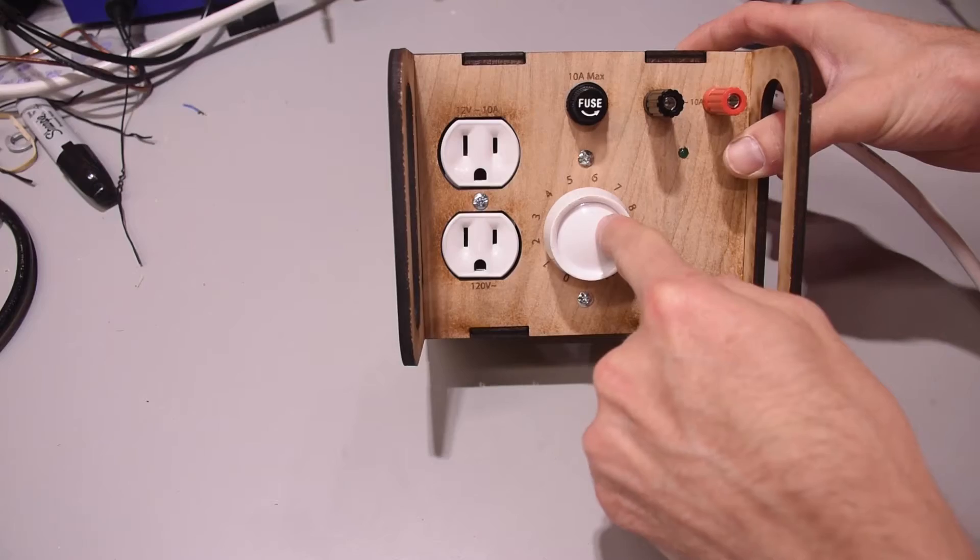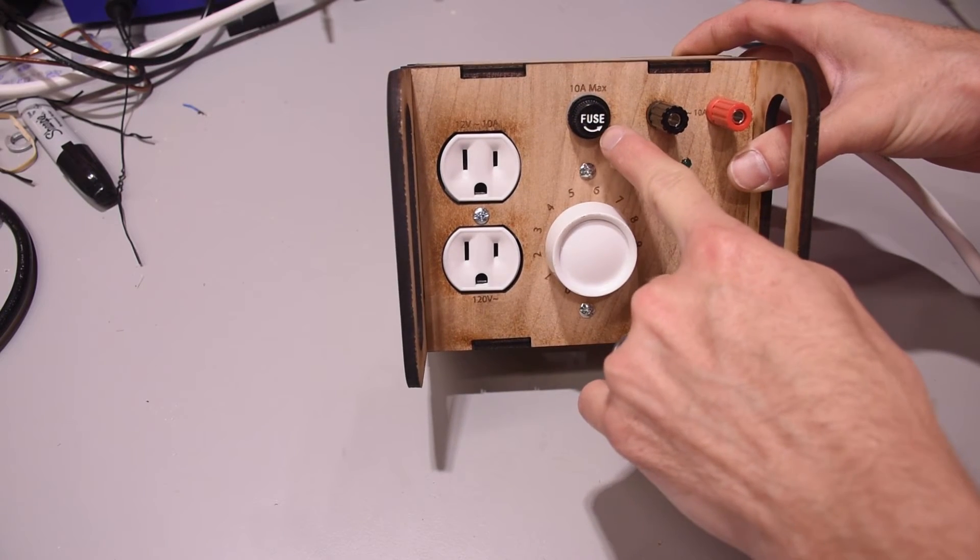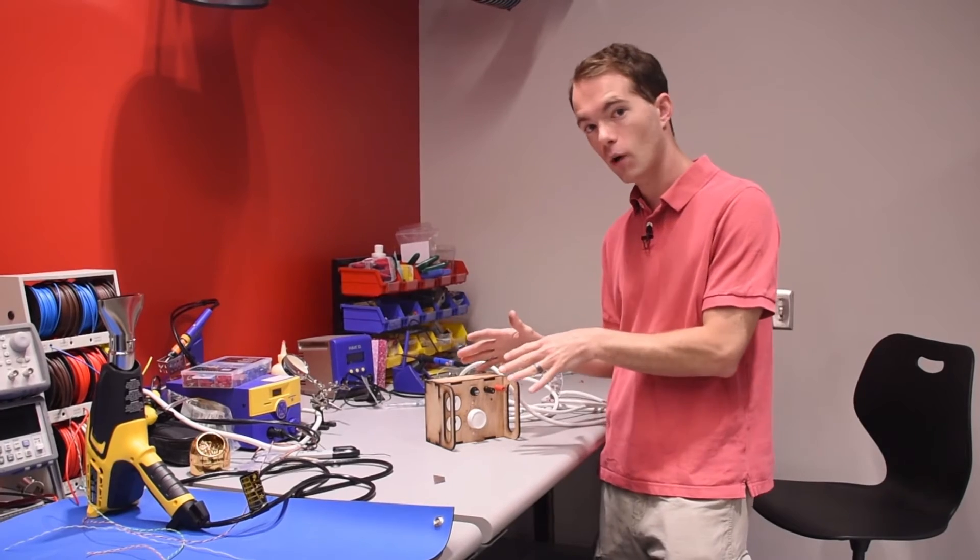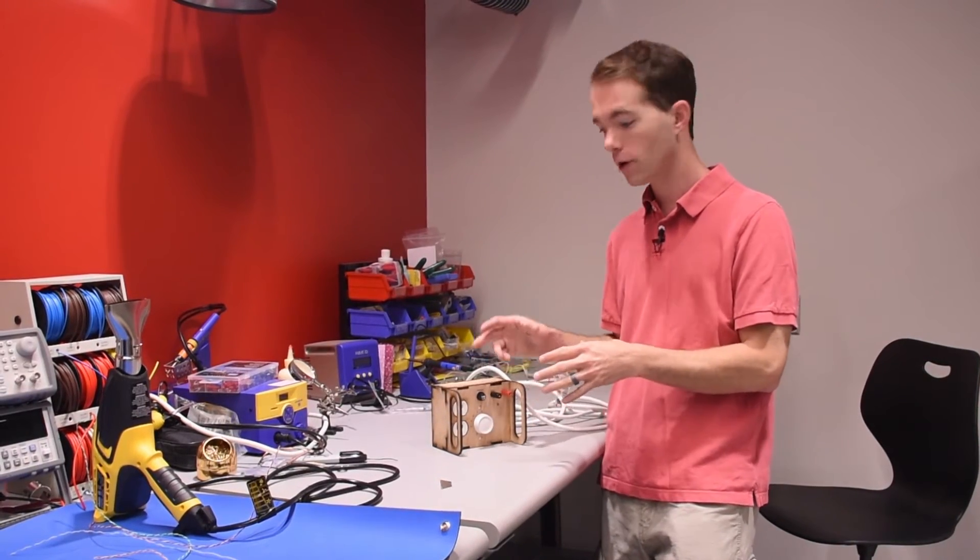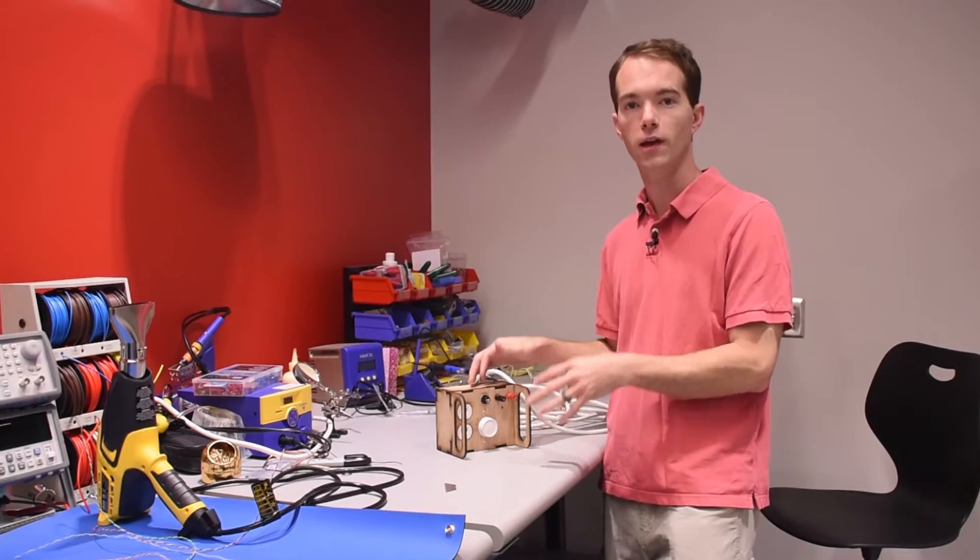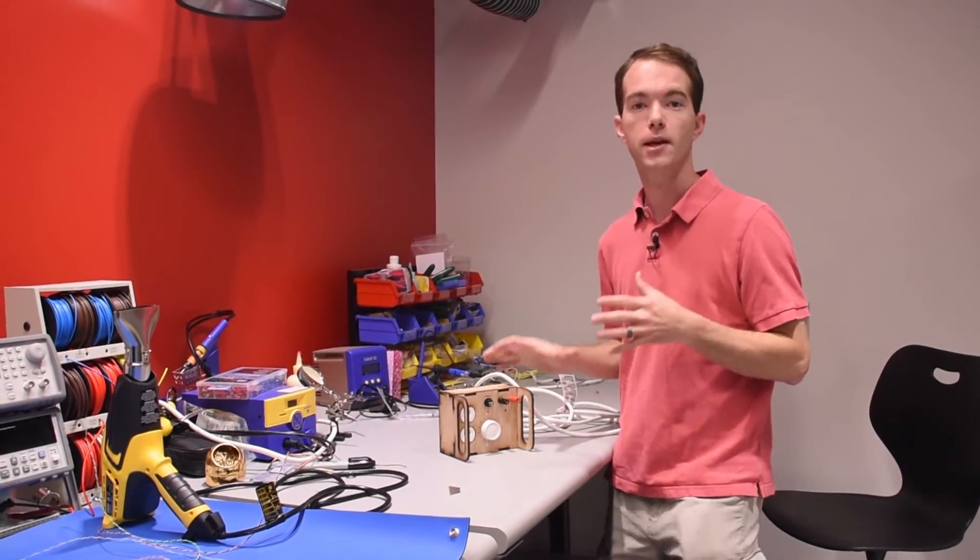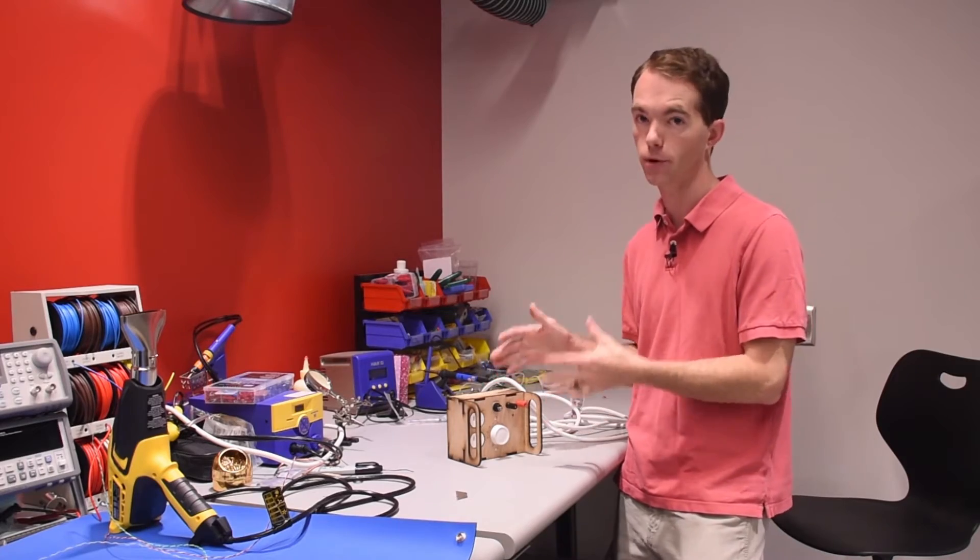So come out of the dimmer switch into the transformer, I come out directly to my 10 amp fuse. Now 150 watts gives me 12 and a half amps on the secondary side, however I'm not going to put a 12 and a half amp fuse in. I'm only putting a 10 amp fuse in because I want to make sure that I don't blow my transformer, because the fuse is a heck of a lot cheaper than a transformer.